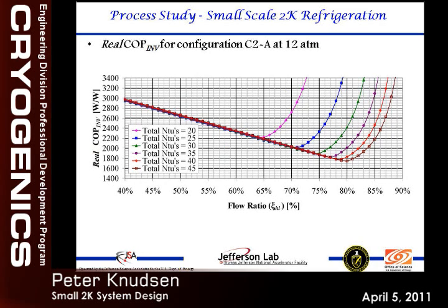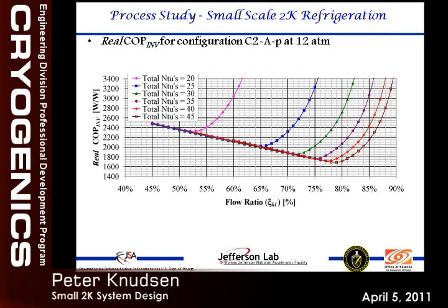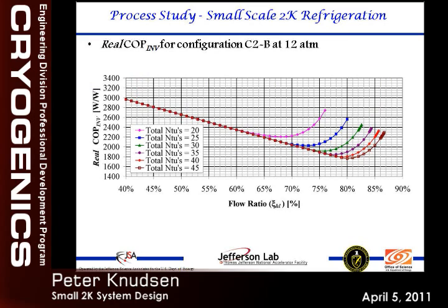This is the real COP inverse. The difference between this one and the ideal one that we looked at before is that this has got more of a knee to it. Likewise with this one, and likewise with that one. So those were the three ideal COP inverse curves for those configurations, and then the 3 real ones.